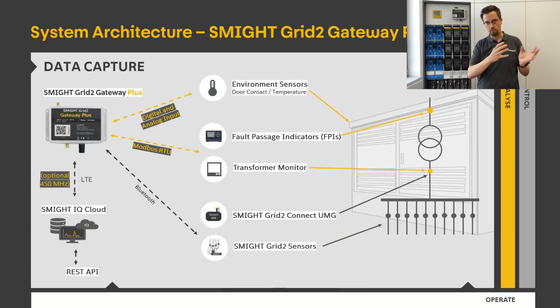With the Gateway Plus, it's going to have all of the old capabilities from our standard gateway, also bringing in the ability to read out all of these other devices which you would typically find in a substation. Another little piece that's turned up on the diagram is the optional 450 megahertz piece on the communication between the gateway and the cloud. I'm going to go into this in a little more detail, but just to touch on it, this is essentially a private network for the utilities in Germany. I think some other countries are also implementing this band, so that in the case of a power outage, you have a network that's still operational because it's buffered with batteries.